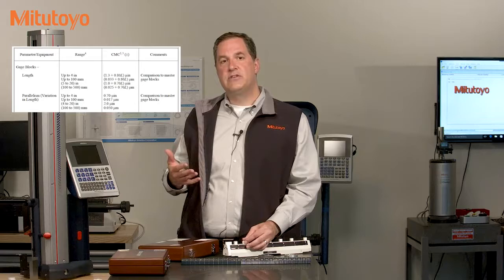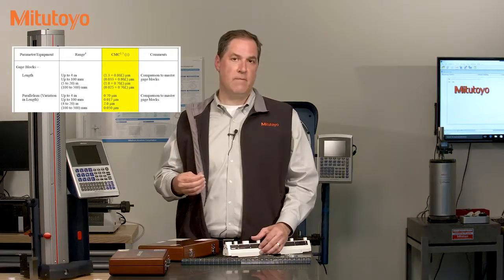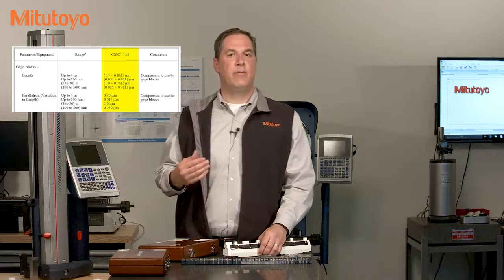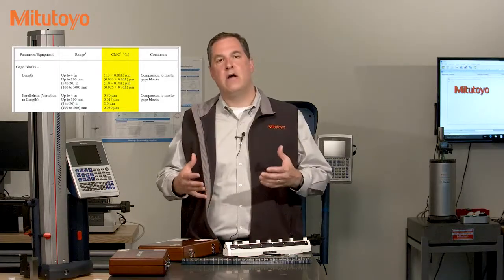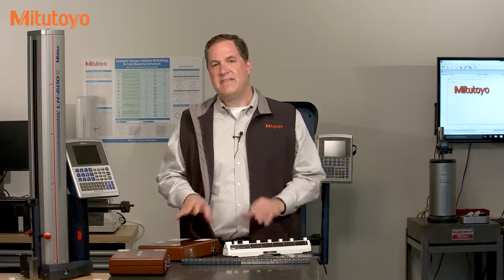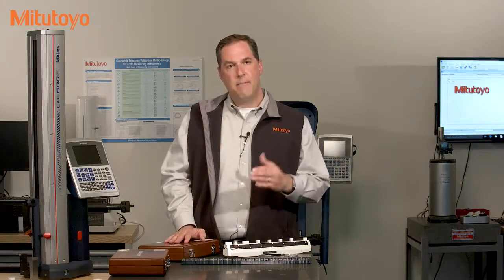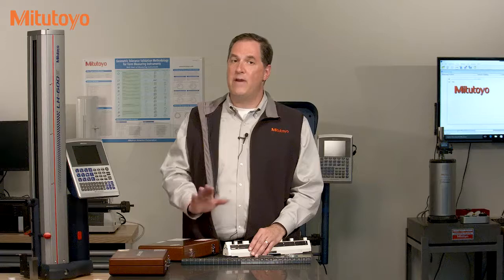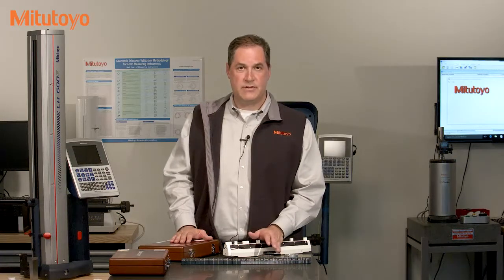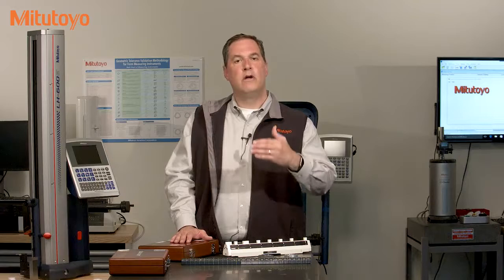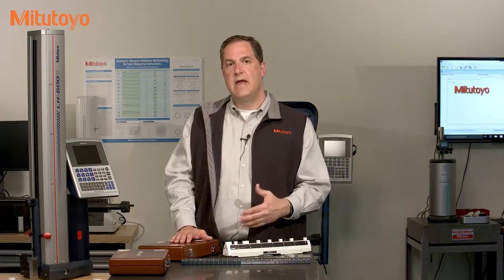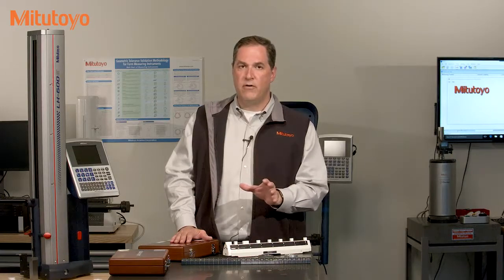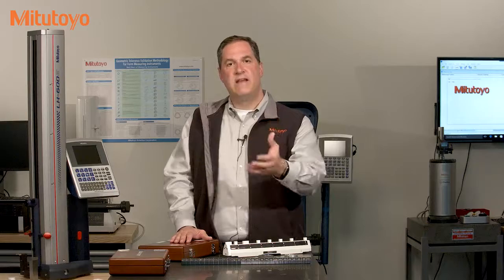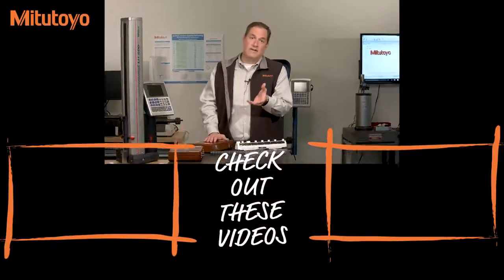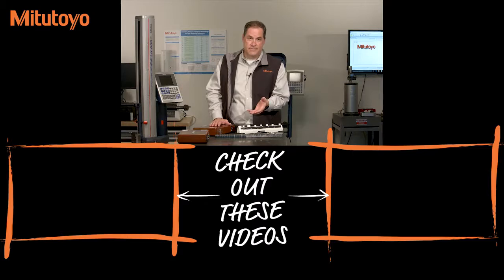The scope also lists what's called the CMC, or the Calibration Measurement Capability, which is a measure of how well our lab can calibrate something. The CMC is also sometimes called the Best Measurement Uncertainty. Now, we're not getting into what uncertainty is in this episode, but let's just say that a lower uncertainty or a lower CMC means the lab can measure more accurately. Scopes are pretty powerful and a very easy way for you to vet calibration suppliers, or as I like to do, to spy on my competition.